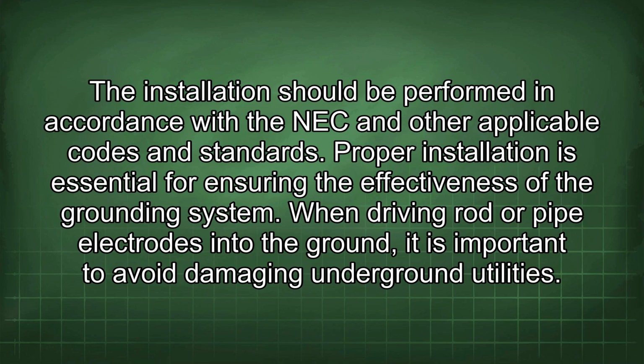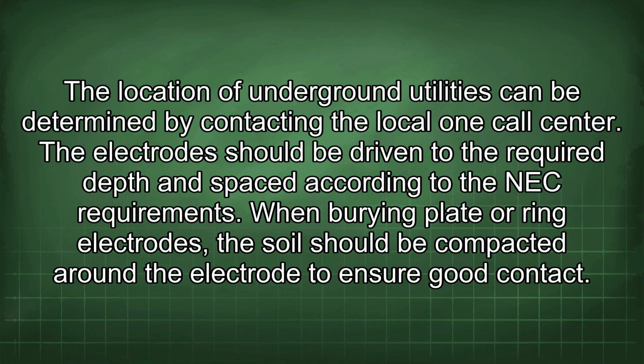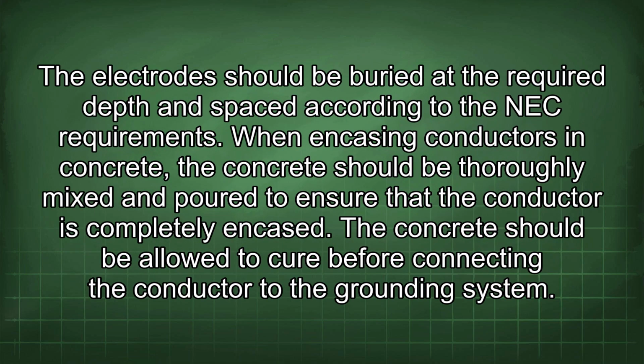When driving rod or pipe electrodes into the ground, it is important to avoid damaging underground utilities. The location of underground utilities can be determined by contacting the local one-call center. The electrode should be driven to the required depth and spaced according to the NEC requirements. When burying plate or ring electrodes, the soil should be compacted around the electrode to ensure good contact. The electrode should be buried at the required depth and spaced according to the NEC requirements. When encasing conductors in concrete, the concrete should be thoroughly mixed and poured to ensure that the conductor is completely encased. The concrete should be allowed to cure before connecting the conductor to the grounding system.